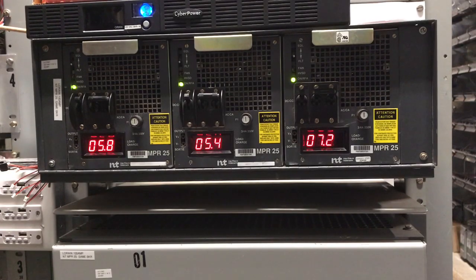Under normal commercial power conditions, most North American power plants operate at negative 48 volts if there's no commercial power, sustained for a long period — several hours. When commercial power is available, we generally float the batteries around 52.4 to 52.5 volts, depending on local telco specifications. In my case, I'm set at 52.4 volts.